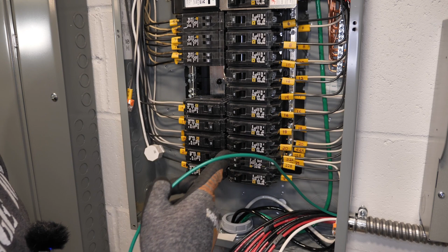If you're going into a main panel, your neutral and ground are already connected. Since this is a sub panel, mine are separated. So the green ground wire is going to go over to this ground bar, and the shared neutral is going to go to the neutral bar right over here.